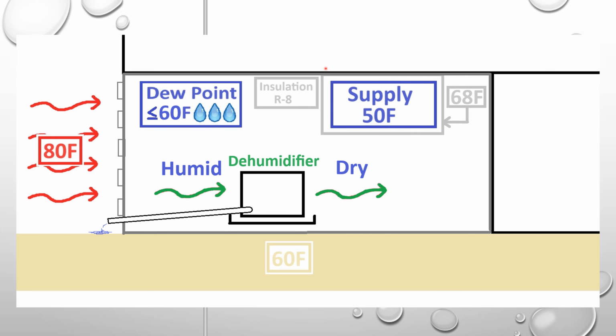Another question I've gotten before is, why is the ductwork even in here to begin with? In all reality, I 100% agree with this. Ductwork should always go into conditioned areas, which would be the house up here, because you wouldn't have any of these issues at all. Up here, the dew point is lower. It's about 50 to 60 degrees, like it is in this crawl space, but it's inside the house. And you don't have issues inside the house at all from the ductwork sweating. So if you could put it in the house, that would be the best option you could have.